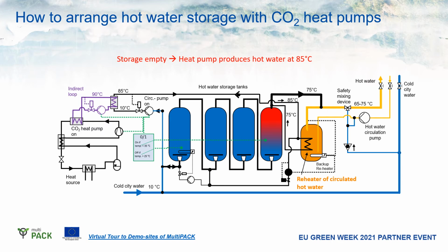This is an example of a heat pump on the left hand side, a very simplified CO2 heat pump. There is an intermediate loop, an indirect loop, to separate the high pressure CO2 side from the domestic hot water part of this side. In this case, I show you 4 storage tanks, which are characterized by having a serial connection. While the water is entering, the cold water can enter on the bottom part, and there has to be a specified diffuser to avoid mixing of the water, a jet flow into the tank. This must be absolutely avoided with heat pumps.